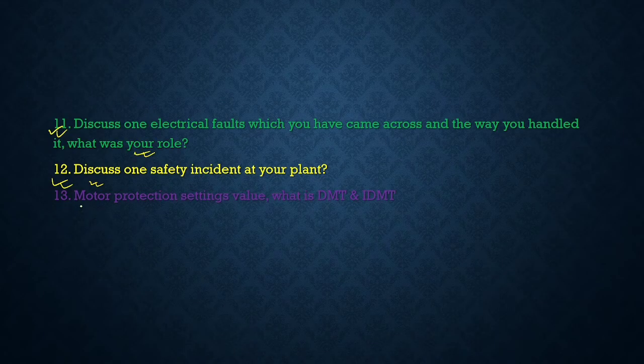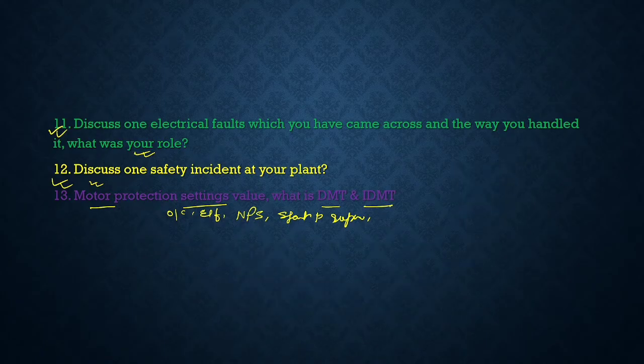Next, they also touch on motor protections, setting values, what is DMT and IDMT, inverse definite time. There are a lot of protections that we use for the protection of the motor, like overcurrent, earth fault, negative phase sequence, and startup supervision. If the motor is rated in megawatt, like 1 megawatt, 2 megawatt, then we also use differential protection in the motor, and rotor jam protection. These are the protections that we use, and you can know the settings, like the basic setting percentage we use, like 10% of the CT ratio for overcurrent. We also have protection.